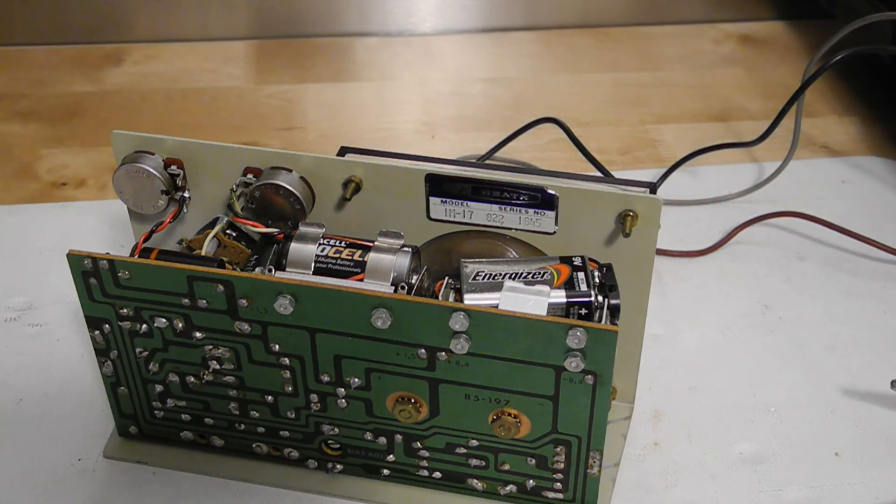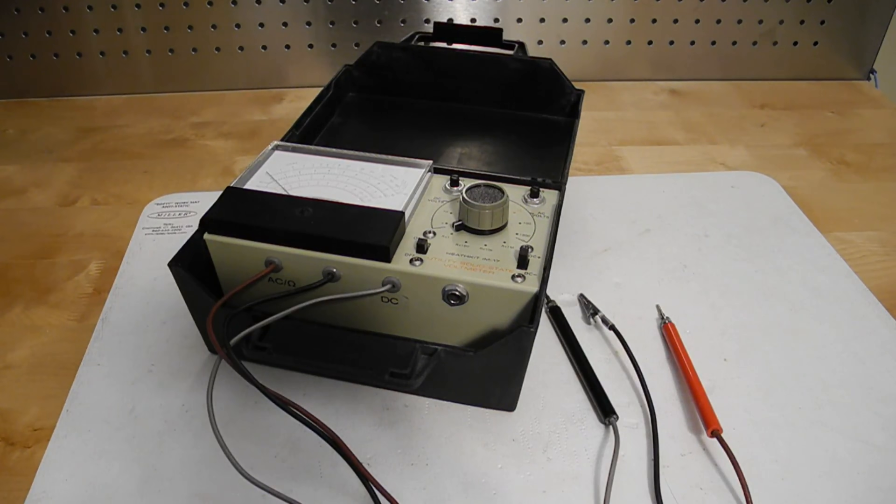Since the original mercury battery is no longer available, I wired in a battery clip so it can use a standard 9 volt battery. I performed calibration as per the manual.